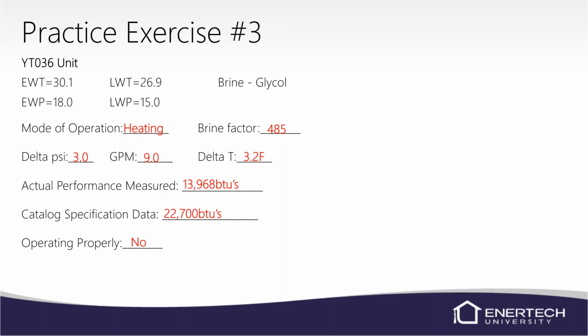If you are in second stage, then we'll have to go ahead and move on to the refrigerant side of things and look at the refrigerant pressures. We know we've got good airflow. We know we've got proper water flow. So it has to be in the refrigerant circuit somewhere.